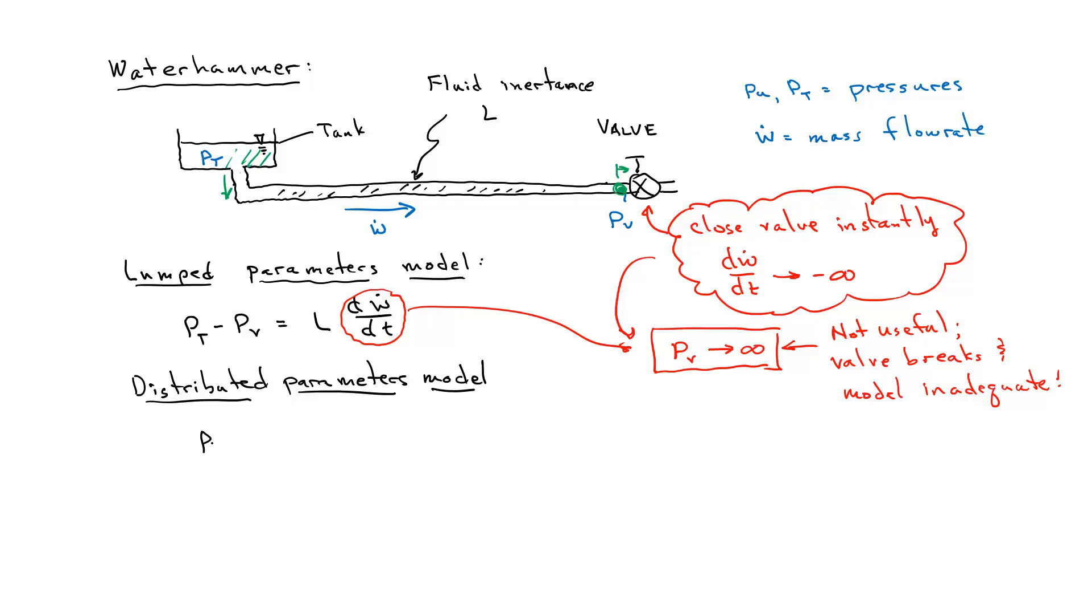In this model it turns out that the valve pressure is proportional to the speed of sound times the fluid velocity before I close the valve. So this is the product of sound speed times the original velocity. Sound speed is kind of a measure or an indicator of how compressible a fluid is. If a fluid is fairly compressible, it'll have a low sound speed. If it's incompressible, it'll have a high sound speed.